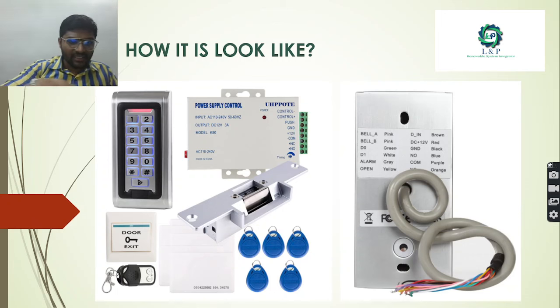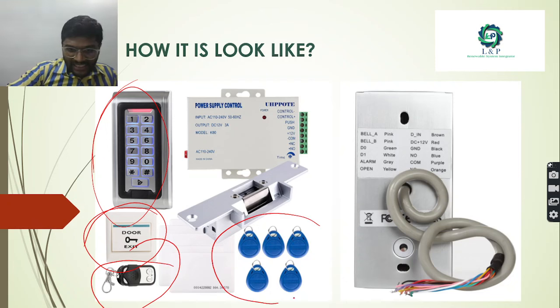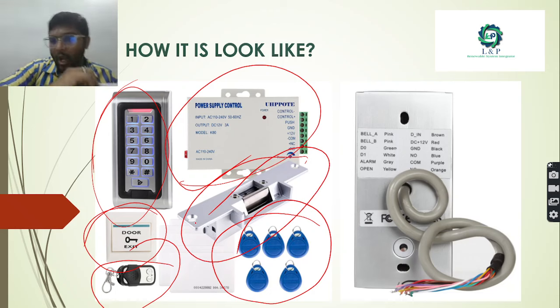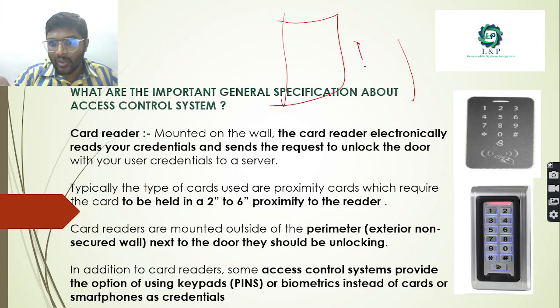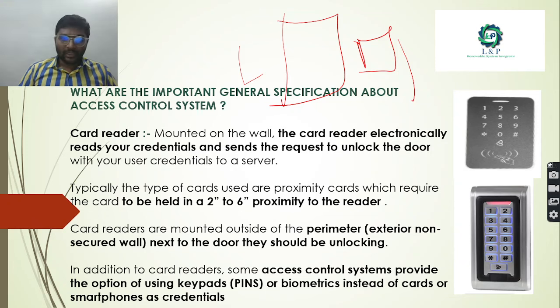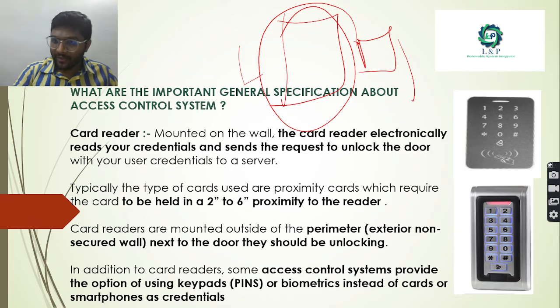Here we have a card reader and an emergency exit. Keys and cards can also be used to access doors. The output — the lock — is also visible here. A card reader is mounted on the wall, typically on the right or left side of a door. It electronically reads credentials and sends the request to unlock the door. It is held 2 to 6 inches in proximity to the reader and installed at the outer perimeter of the doors. For PIN-based access, keypads are also available.